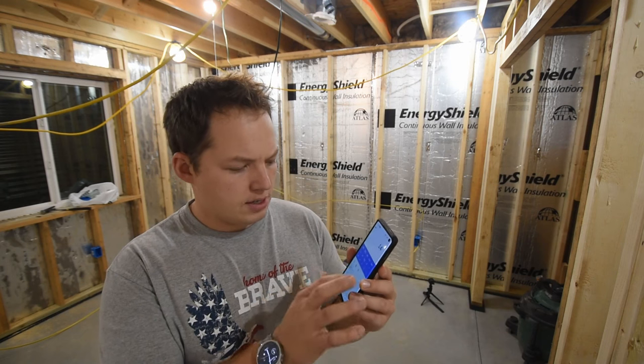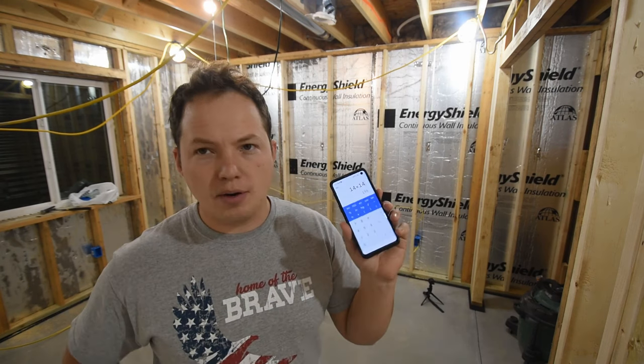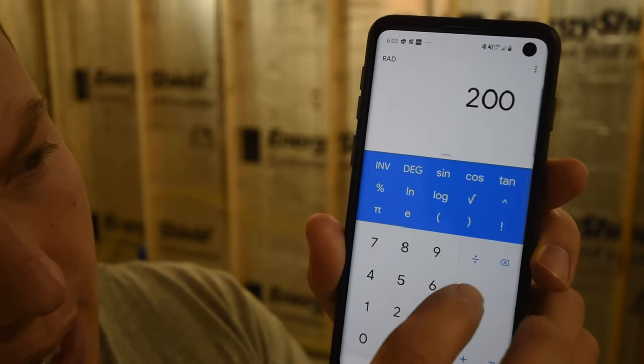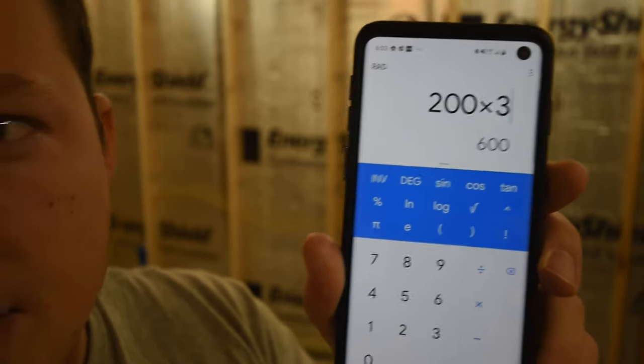So this little bedroom that we're in right now is about 14 by 14, so we're going to multiply that and come up with 196 square feet, or let's just say 200 square feet. Now with that information, we multiply the square footage by 3 VA, or volt amps, or basically watts. So we'll take our 200 times 3, which gives us 600 watts.